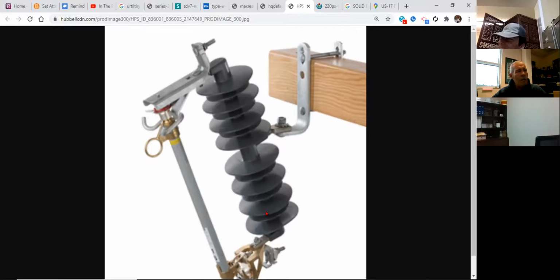Kind of. Lightning strikes the line - let's put it this way. If lightning strikes my tap line and I don't have lightning arresters at my transformer locations, they're going to get damaged from the lightning strike. Then I would put a lightning arrestor at my fuse tap location. But for protection, and to be better capable of protecting my transformer, I'm going to put a lightning arrestor on my switch at every transformer location, just like we do at the field. Since I've done that at every transformer location on my tap line, I don't need to protect the tap line anymore - I don't need an arrestor at this.